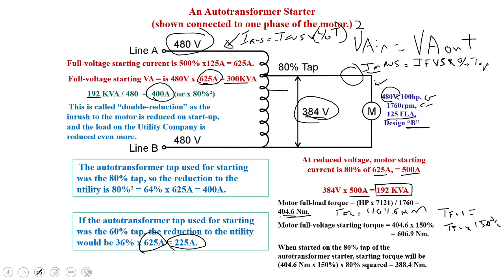So if I start on the 80% tap of this auto transformer, I'd take my full voltage starting torque here, and I'd have to multiply it by 80% squared, or 0.64, in order to figure out the new maximum torque it'll produce on startup. And in this case, that drops it down to 388.4 Newton meters.